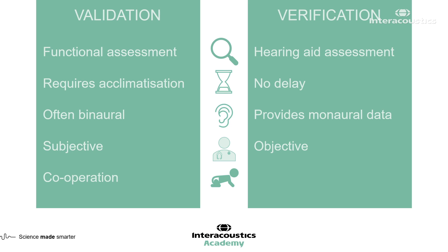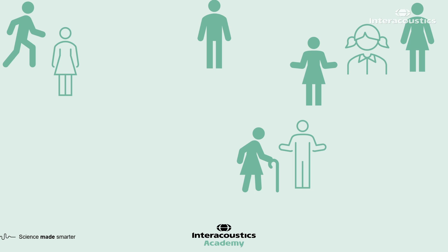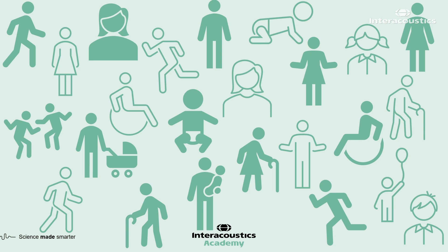Real ear measurements provide objectivity and require minimal cooperation, even in young infants, children, or patients who are not able to sit still for full real ear measurements — we have the option of coupler measurements. So why does verification matter? We have huge variations between people: differences in ages, genders, sizes, and hearing losses. Our real ear measurements and our verification process allows us to overcome that.